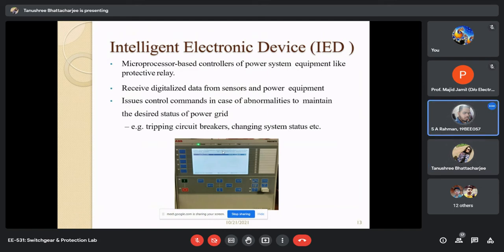And ma'am, what is the difference between that IED and IEC 61850? IED is the device and IEC 61850 is the protocol. Protocol means whatever configurations you give inside the substation, configuration like we do computer programming. IEC 61850 is an XML markup language, like HTML, you know. In the same way, coding is done in HTML or Notepad. Okay, so these are the configuration files. The IEC protocol is a set of configuration files which we configure inside the IED, inside the merging unit, and inside whatever substation devices, through this protocol. And IED is the device, okay, this device is the IED.